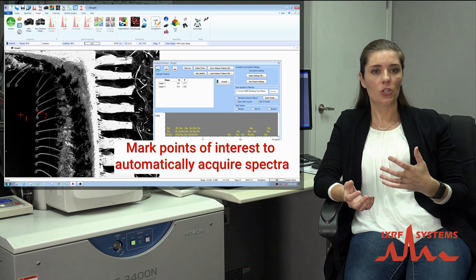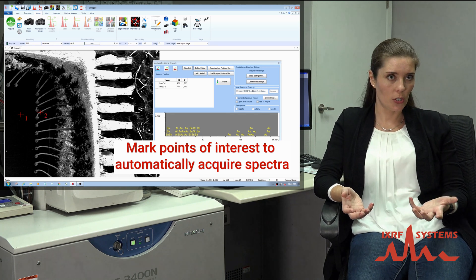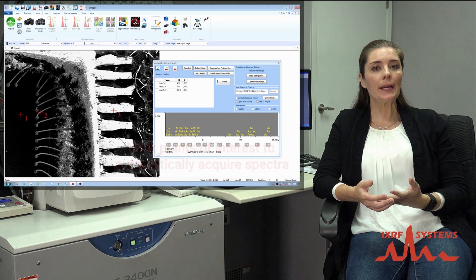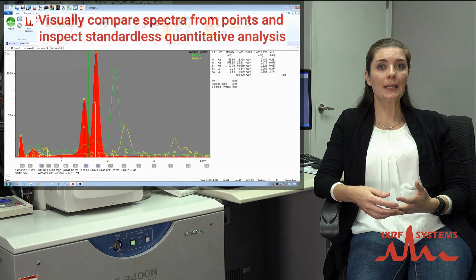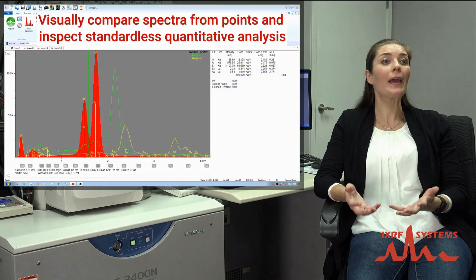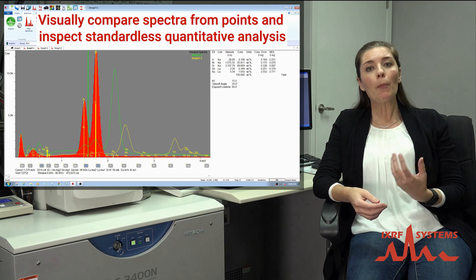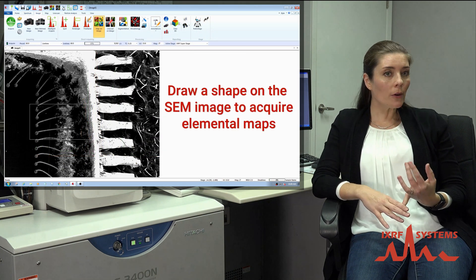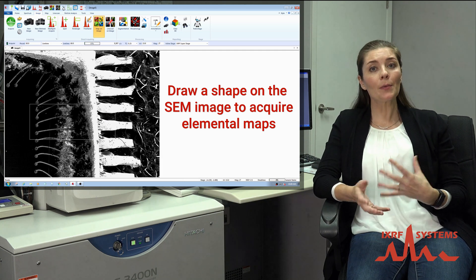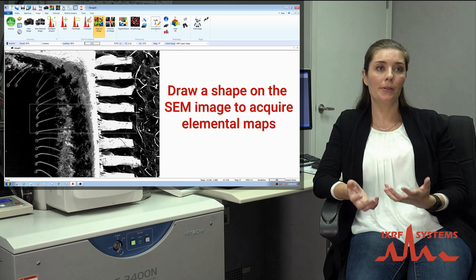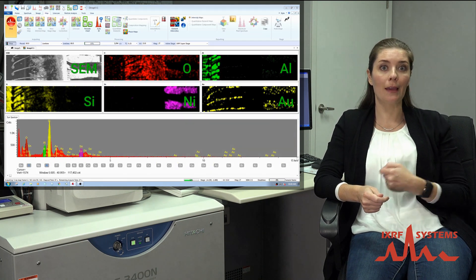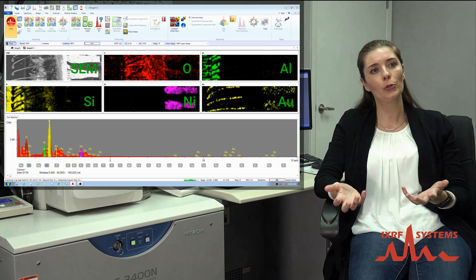To get to full quantitation, that's where we're looking for those concentrations, and we are limited a little bit. EDS, even under the best circumstances, is considered semi-quantitative even if we have access to standards. Part of that is because of our limit of detection — depending on your matrix and your element, our limit of detection is about a thousand parts per million. So it's really hard to call that fully quantitative if I can't split hairs and tell the difference between, say, 3.1% and 3.2%.